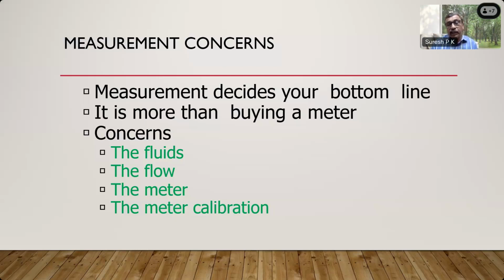Then the meter, of course, and the meter calibration. The meter is as good as its calibration, otherwise it is only a metal piece. If you don't calibrate it properly, then every instrument is a metal piece. I won't say you can rely on the reading of the instrument unless it is calibrated properly, with a proper system, with a proper instrument. So meter calibration is all the more important. The fluid flow measurement accuracy depends on the fluid, the flow meter, the flow, and the calibration. These are the major four concerns when you are making a fluid flow measurement.